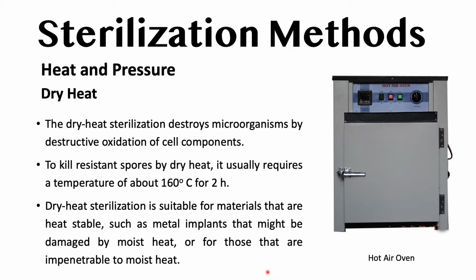Dry heat. The dry heat sterilization destroys microorganisms by destructive oxidation of cell component. To kill resistant spore by dry heat, it usually requires a temperature of about 160 degrees centigrade for 2 hours. Dry heat sterilization is suitable for material that are heat stable, such as metal implants that might be damaged by moist heat, or for those that are impenetrable to moist heat.